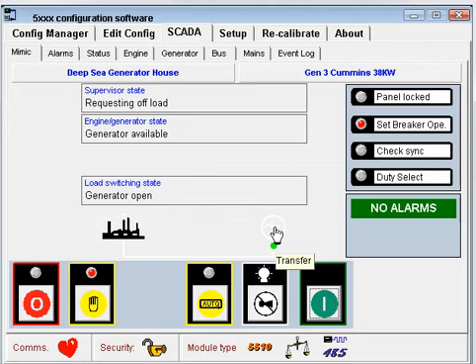If the engine speed falls instead of rising, you need to select governor output reversed in the module's configuration.